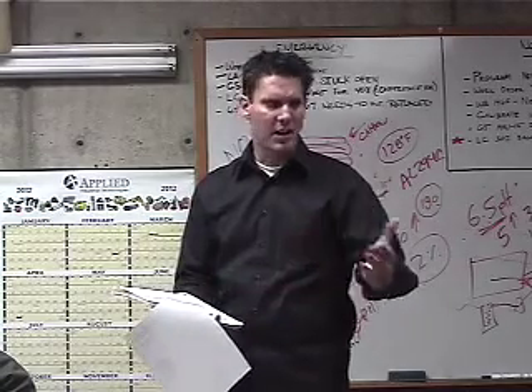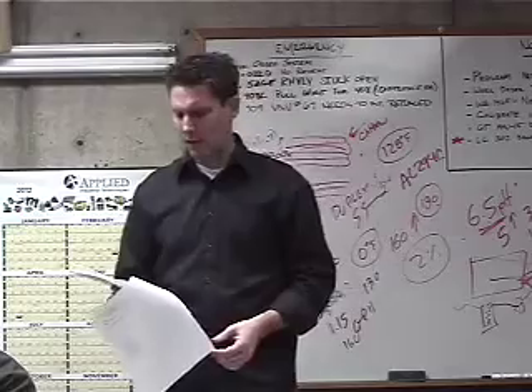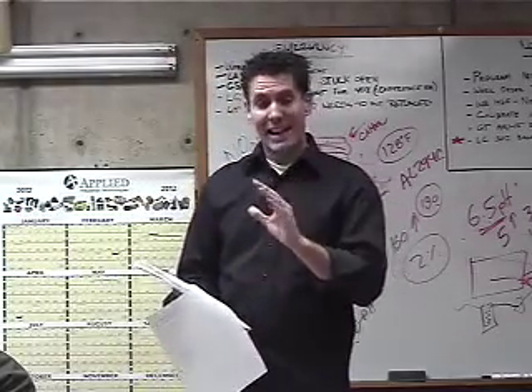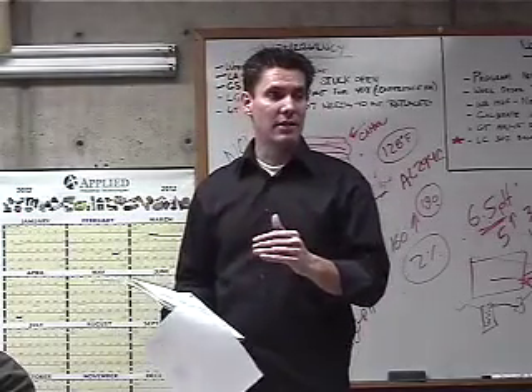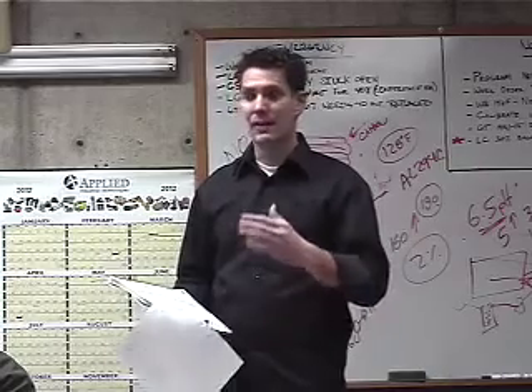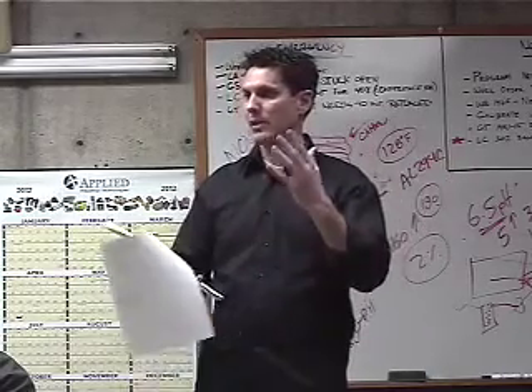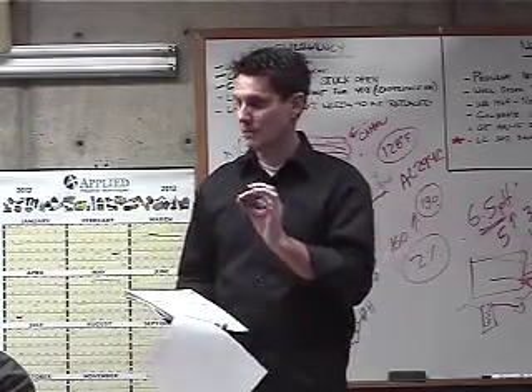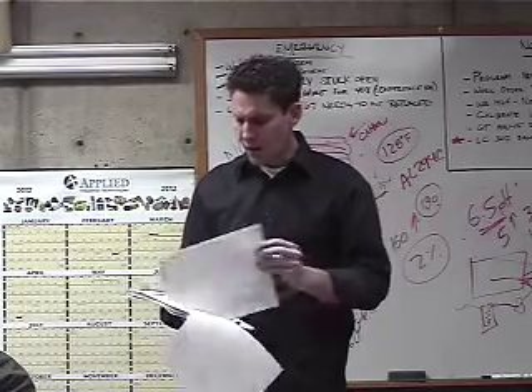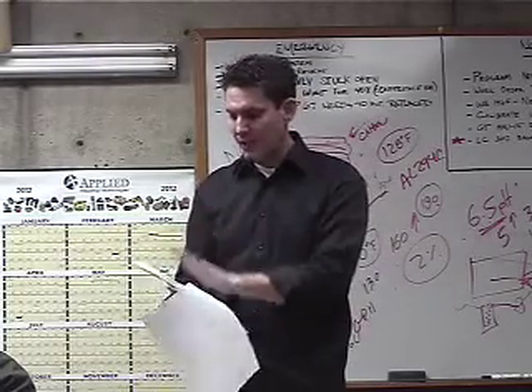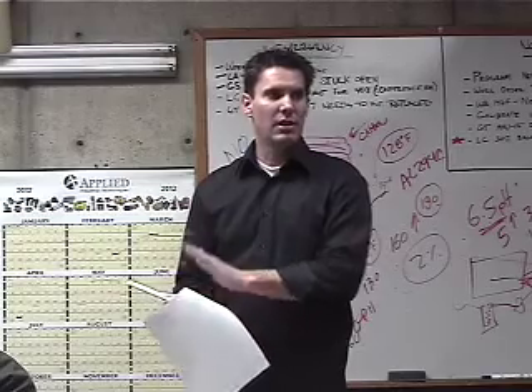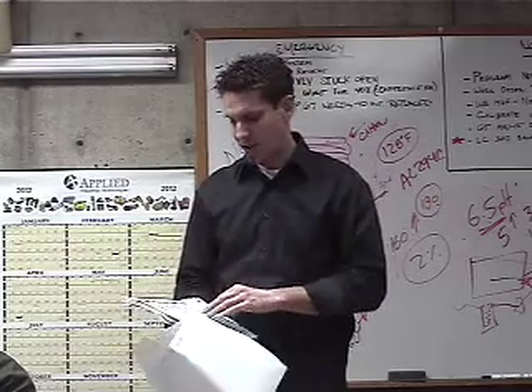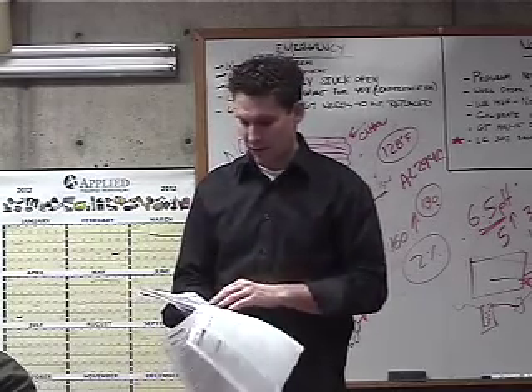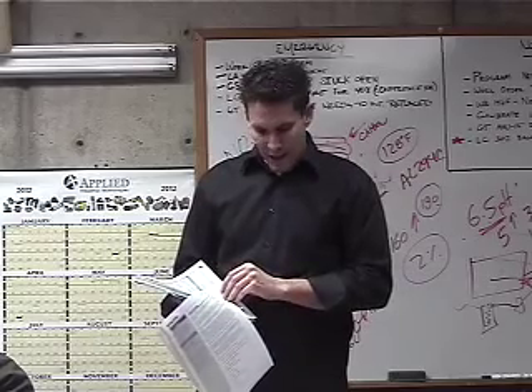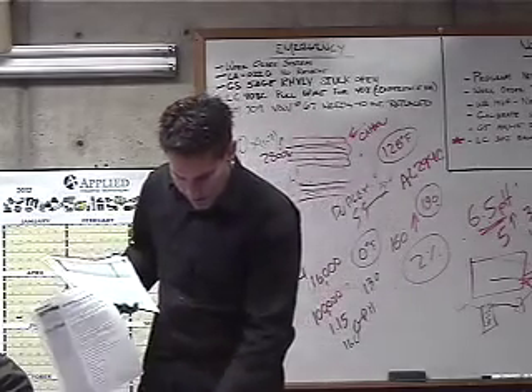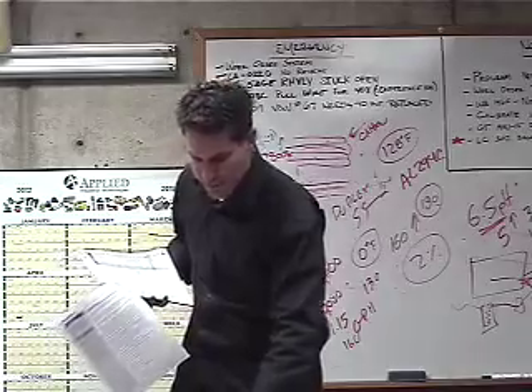Yeah, I'm sure you've got to be hiring somebody to come in and check them out. Yeah. Okay, but again, these things are not as forgiving. Any high efficiency product is not as forgiving as just the old standard atmospheric or forced draft type appliance. This gets a little bit more temperamental. And as long as you follow the schedule that they give you, then everything will be fine. It's important that you follow the schedule. Okay, so we won't talk about the startup instructions.